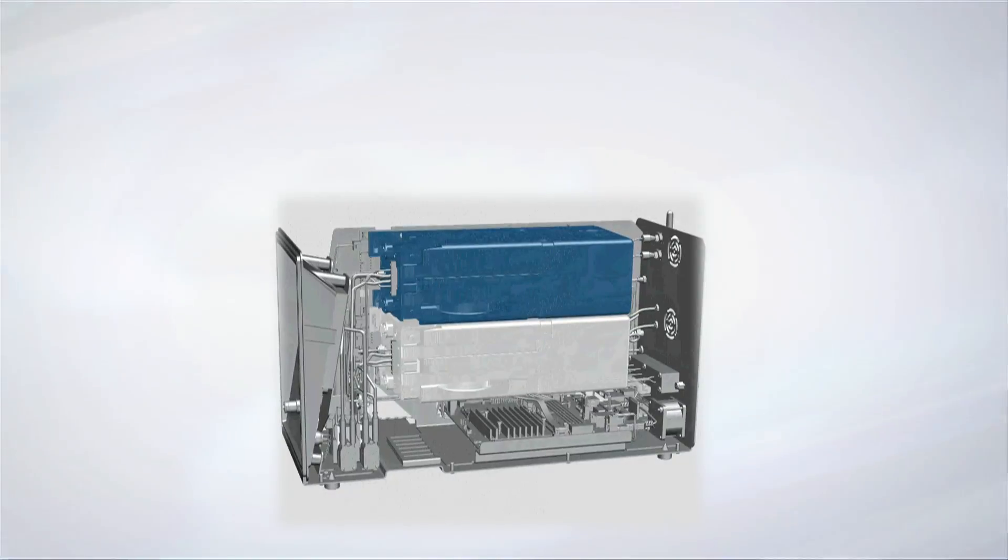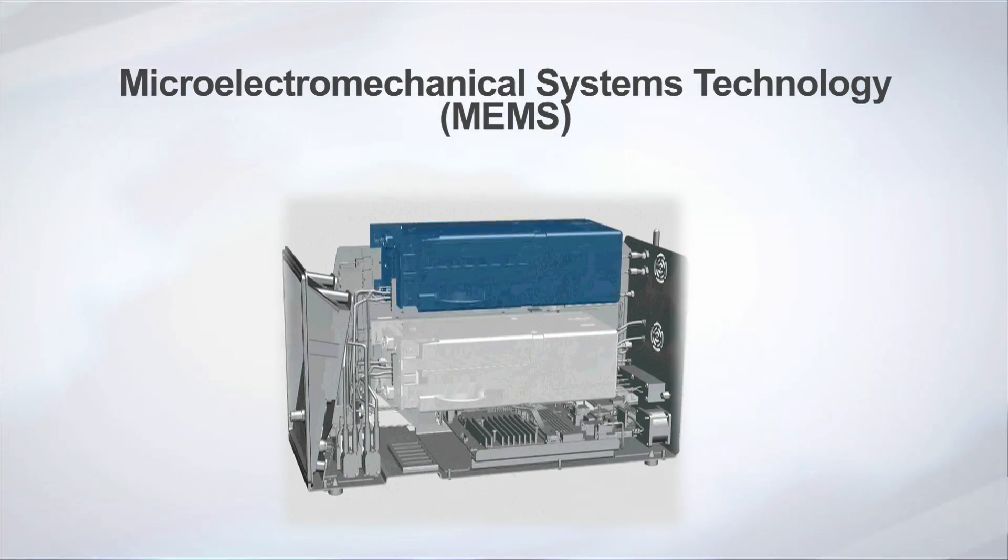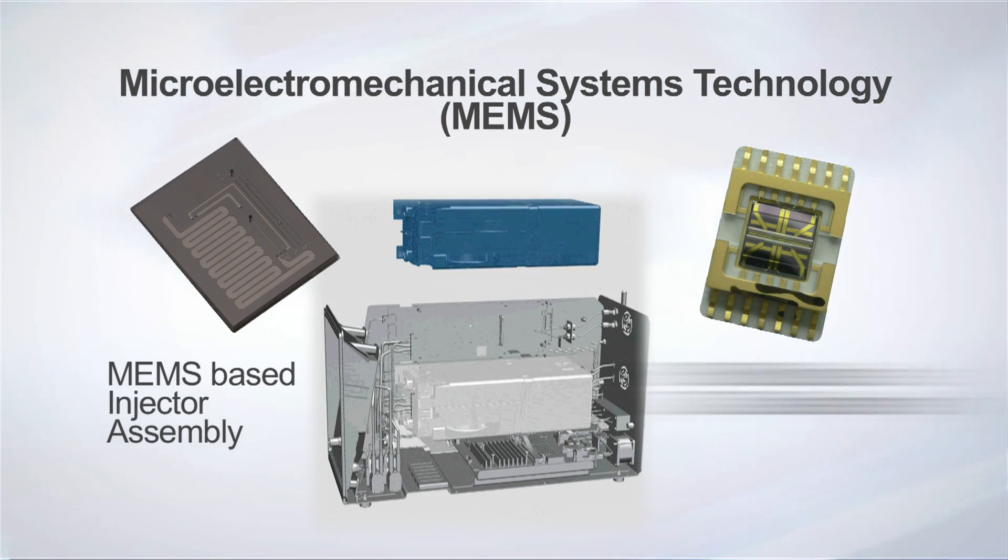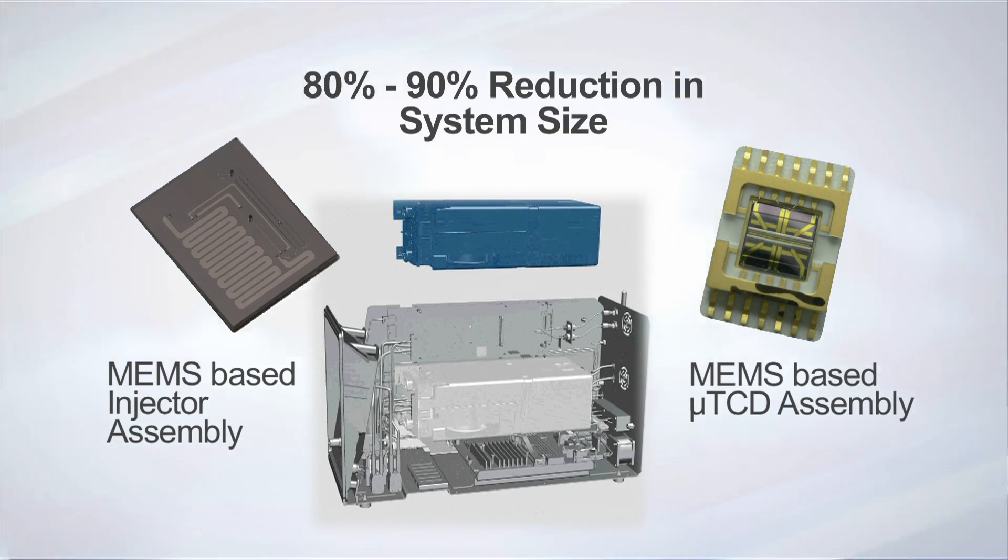Fusion builds on state-of-the-art Micro Electromechanical Systems technology. It miniaturizes the injection and detection subsystems, resulting in 80 to 90 percent reduction in system size when compared to a traditional GC.